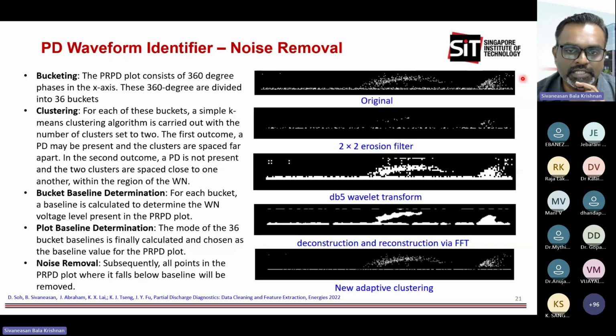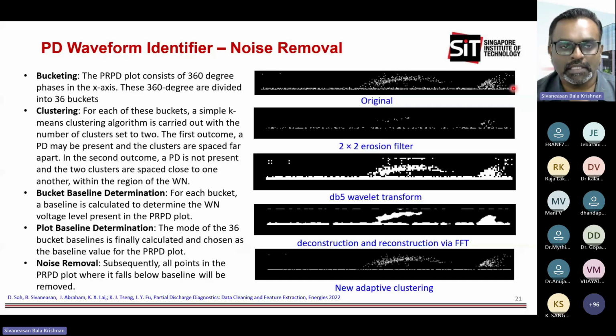For internal discharge, you will see a more one-sided, asymmetric pulse. The third type is corona discharge, typically due to localized discharge near conductors or sharp, pointing edges. This appears as very sharp pulses in both half cycles.